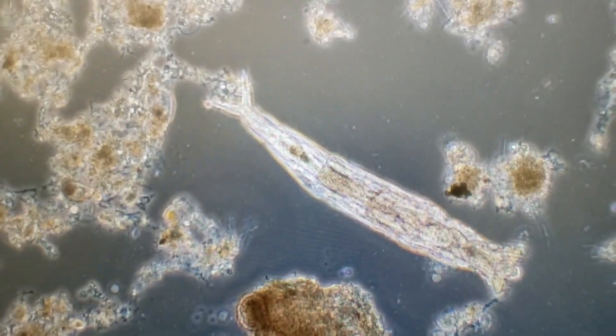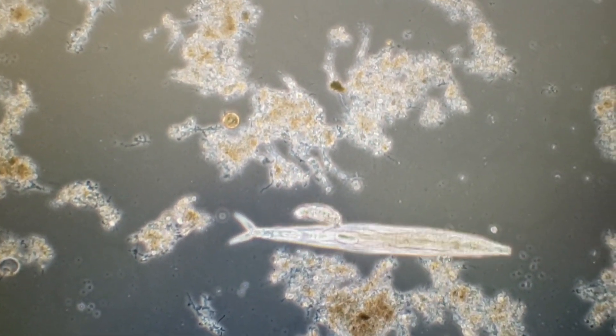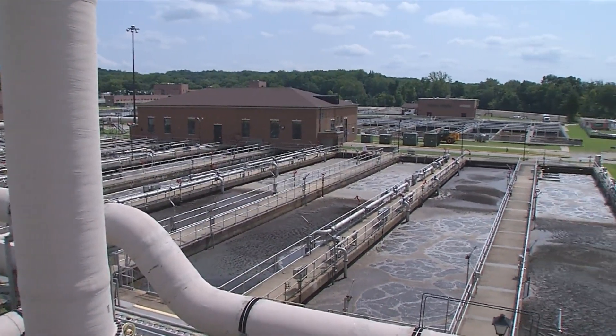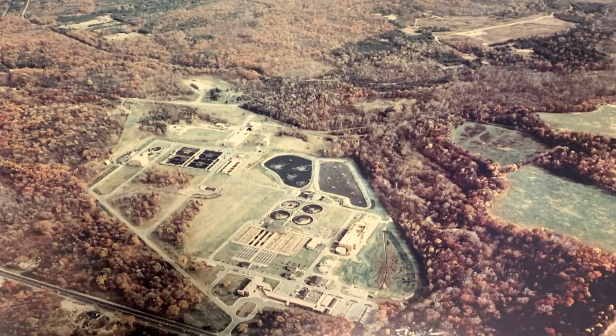After multiple passes through these zones, the microorganisms have been so effective in removing waste — which they use as food — that we need to add supplemental carbon to the system as another food source to keep them alive. After the ASTs, wastewater continues to the secondary clarifiers, another settling process, where we are removing solids and microorganisms. Some of these settling microorganisms are returned to the ASTs to start the process again. In some places, wastewater treatment ends after secondary treatment. Look at the muddy water entering the clarifiers and then how clear the water looks going over the weirs into the next step — those microorganisms do a great job.